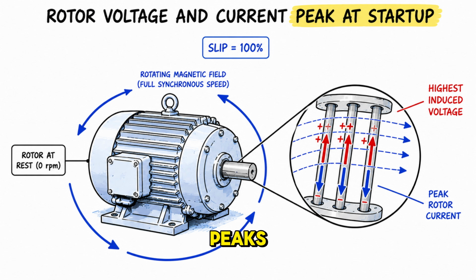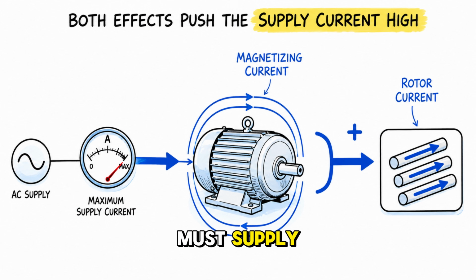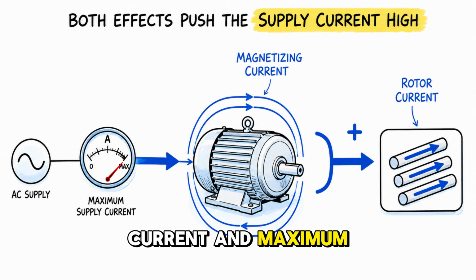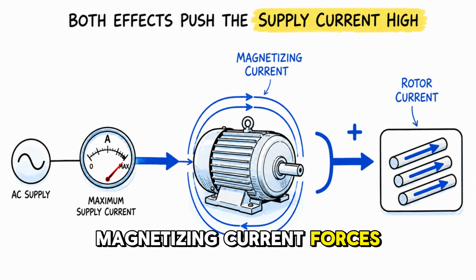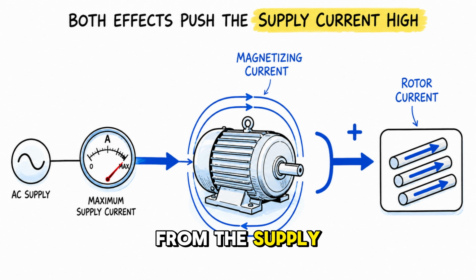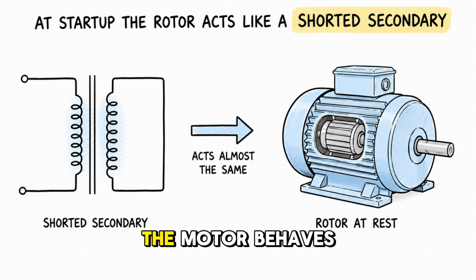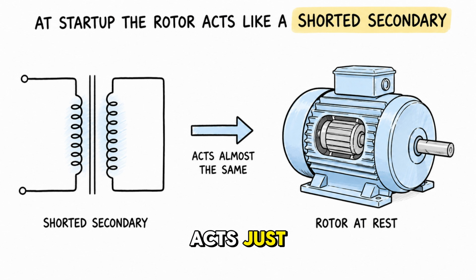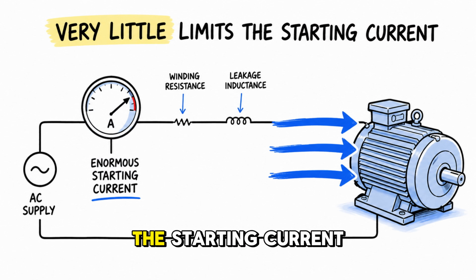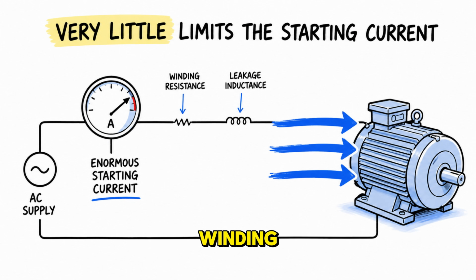The rotor current peaks. At the same time, the stator must supply the intense magnetic excitation to build this entire field from zero. This combination of maximum rotor current and maximum magnetizing current forces the stator to pull maximum current from the supply. At this exact moment, the motor behaves almost like a short-circuited transformer. The stationary rotor acts just like a shorted secondary winding. The starting current is limited only by the winding resistance and leakage inductance, which are both incredibly small. For this reason, the starting current is absolutely enormous.